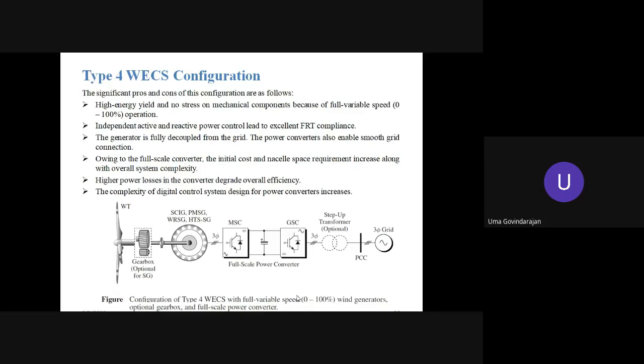The generator is fully decoupled from the grid because we have one machine side converter, MSC, and one grid side converter. And hence a full rated power converter comes between the grid and the machine, and hence the machine is completely decoupled, and the FRT requirement of the grid is completely taken care of by the converters.